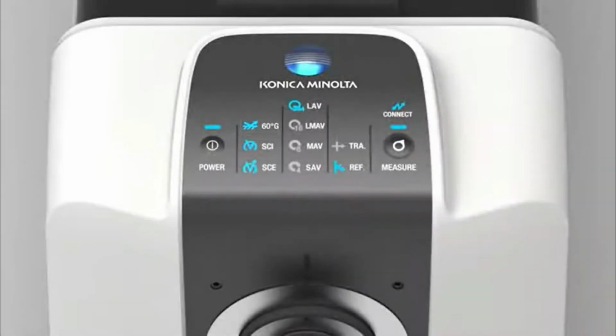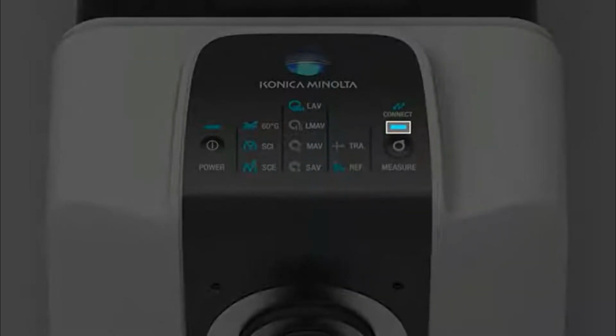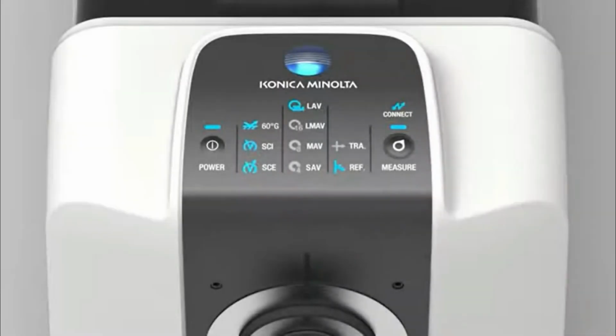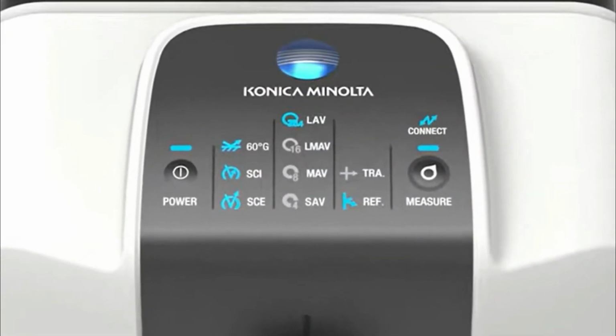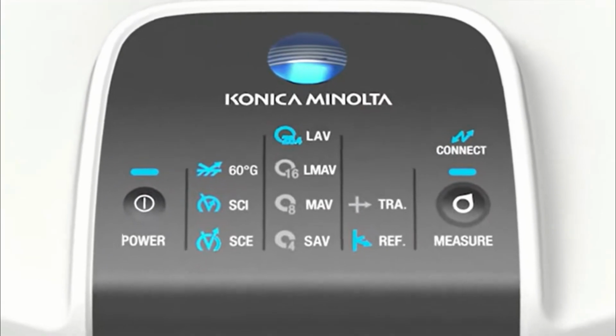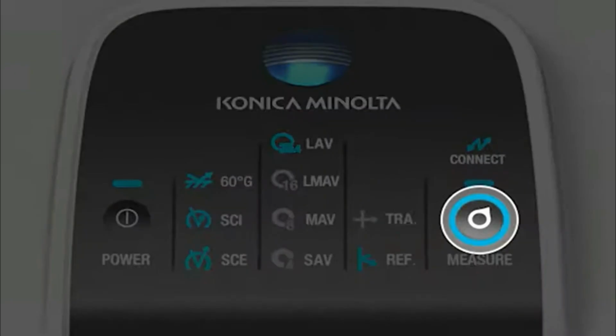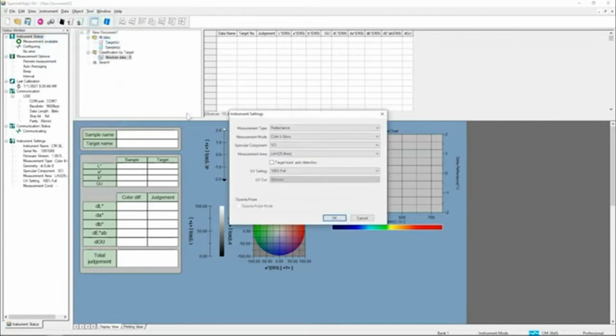When the calibration is finished, you will see the 60-degree gloss symbol light up on the display panel, indicating the gloss unit is calibrated. A blue light over the measure button will also indicate the zero and white calibrations were performed. You can physically press the measure button on the instrument shown here, or use software to activate the measure button electronically without ever touching the instrument.